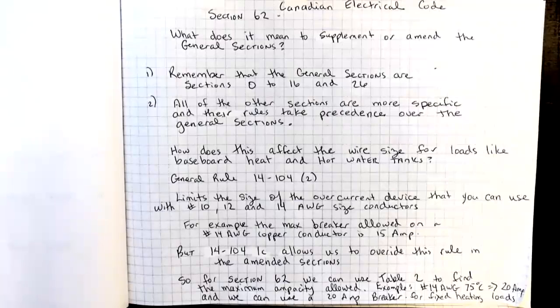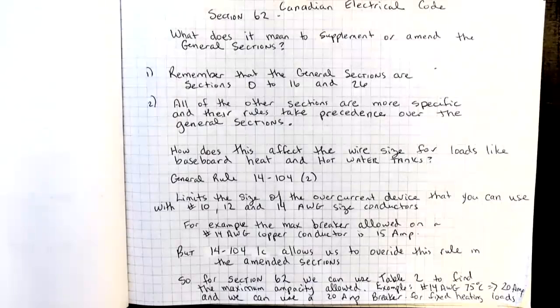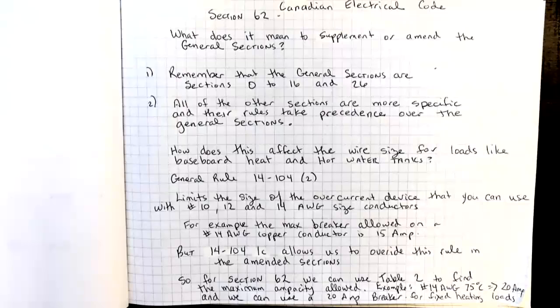So how does this affect the wire size for loads like the baseboard heat and hot water tanks? If we look at a general rule, 14-1042, that rule limits the size of the overcurrent device that you can use with number 10, number 12, and number 14 AWG size conductors. For example, using 14-1042, the maximum breaker allowed on the number 14 AWG copper conductor is 15 amps, even though when we go to Table 2 and look in the 75-degree column, a 14 AWG copper conductor is good for 20 amps.